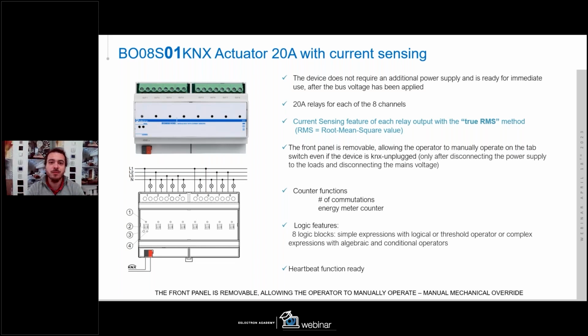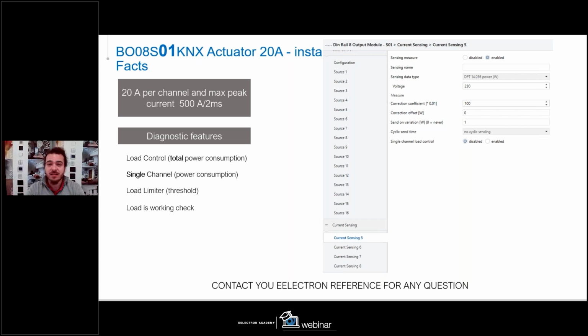We have the opportunity to remove, for example, the front panel, to have a manual override on the switches, or we can enable logic blocks to customize our building with custom functions. The ETS is similar, but in this case we have, of course, the opportunity to have the current sensing of each output, and this can enable some particular functions that nowadays, because of the energy problem, are more and more requested of us. Starting from the total load control, which means that, like in Italy, we have a problem with the energy that can be supplied in a certain residential project. For example, in our houses, by default, we can consume a maximum of 3 kilowatts. After that, we have a blackout in our houses from the electrical service provider.